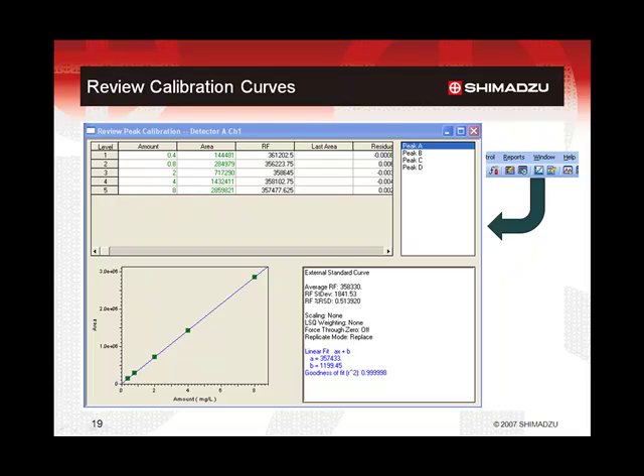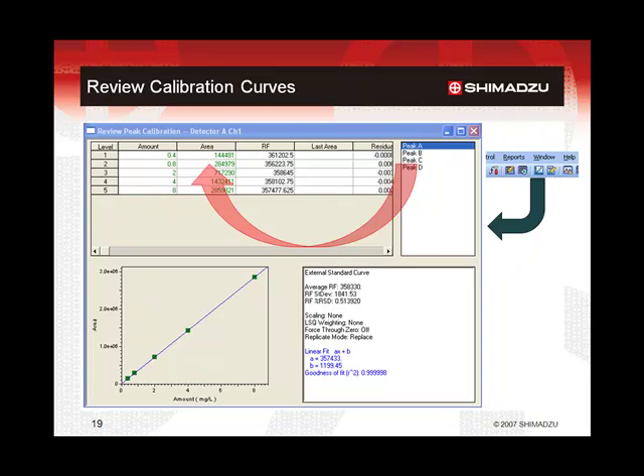By analyzing the sequence, the software will automatically capture the data from the indicated standards. The results of the calibration can be viewed by clicking on the review peak calibration icon in the icon bar. The individual peak data for all calibrated peaks is transferred into the peak calibration table. The standard amounts and the corresponding peak sizes are used to calculate the response factors. By plotting the concentration versus peak sizes, it is possible to see the resulting calibration curve. The regression of this curve yields the equation of the line, the goodness of fit, and the statistics pertaining to the consistency of the response factors. As the sequence is being completed, the method is continuously updated with the calibration results and automatically saved.